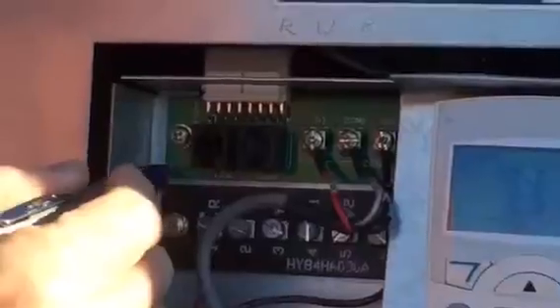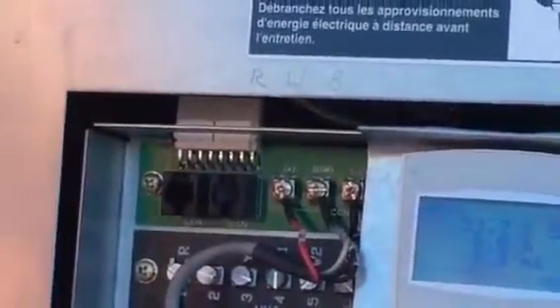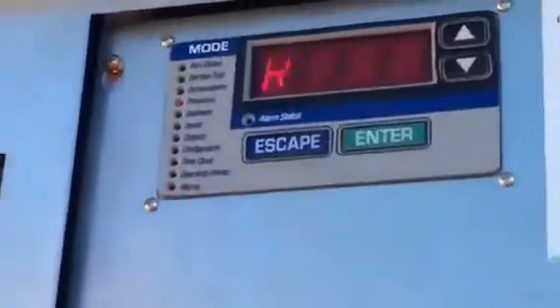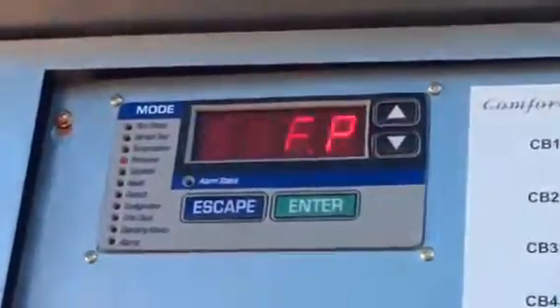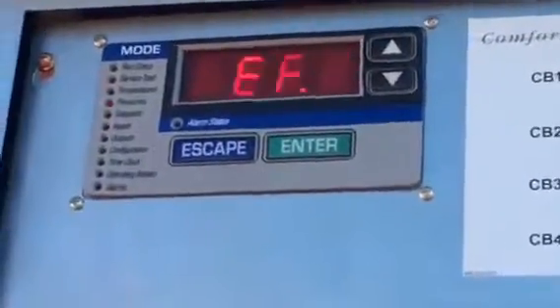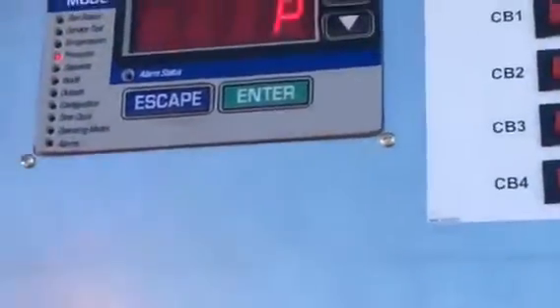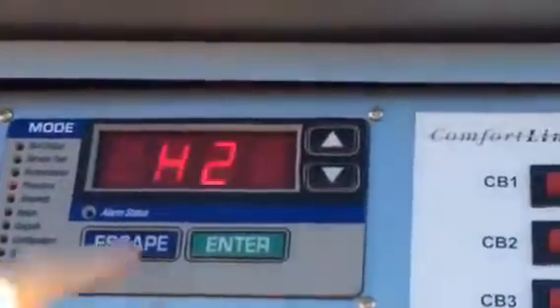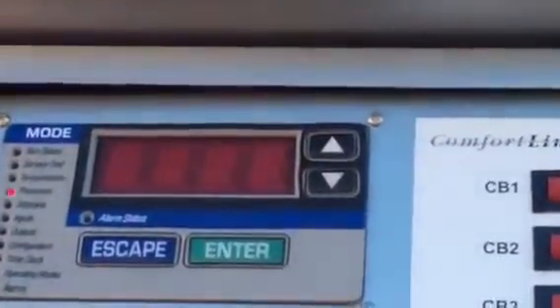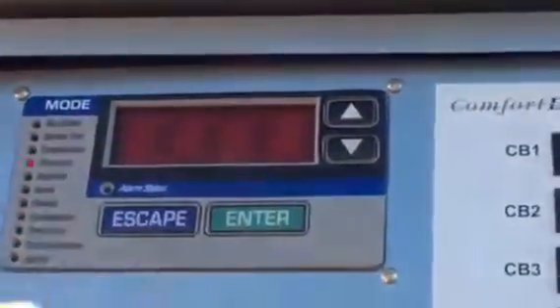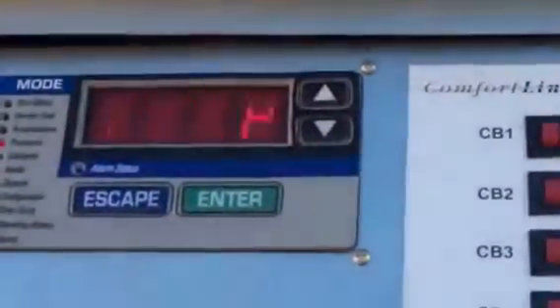This guy here, LEN port. Nav. That one. Nothing will happen if you plug it into the CCN, though I highly recommend don't get in the habit of doing that. But it's going to plug into the LEN. So that's refrigerant pressures. Air pressures are available too. SP means what? Static pressure at 0.22 that I think you mentioned this was run out earlier. And I can always hit enter, escape, and expand it.